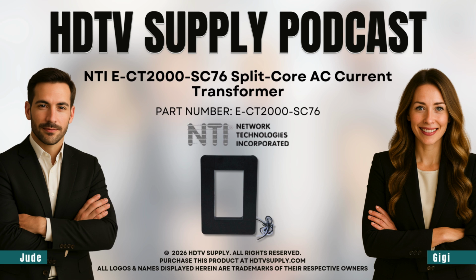Let's unpack that. The first thing that jumps out from a practical standpoint is this split-core design. Why is that so important? It's all about avoiding downtime. With a traditional solid-core transformer, you'd have to shut off the power, shut everything down, disconnect the huge heavy primary cable and thread it through a solid ring. It's a major operation. But with this, the top just pops open and snaps closed around the existing conductor. It's a game changer for installation on live or pre-existing systems.